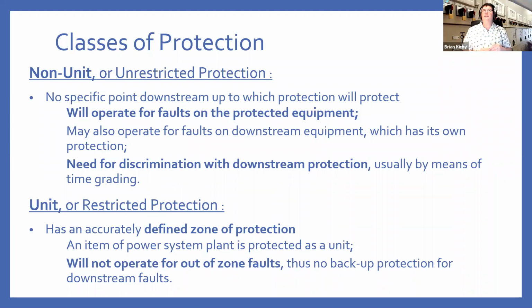Of course, this has its limitations because the equipment on the network will have its maximum loading time that you can withstand the fault. So you need to make sure that your protection is discriminating from downstream events, but also still giving the time protection for your part of the network. If you get to a point where you can't achieve that using time discrimination, you typically would use unit protection. And what this does is it has a specified zone of protection. So you will only operate if the fault is in that zone.